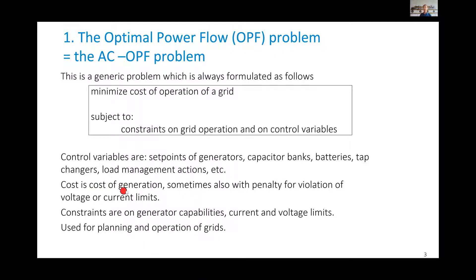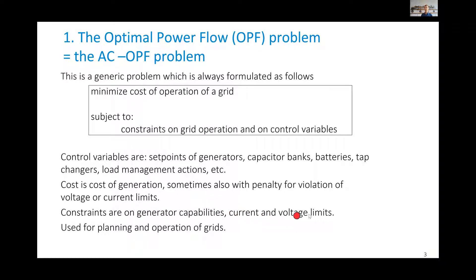The cost is classically the cost of generation. But often it also reflects other objectives — for example, if we are controlling voltage, the cost might reflect how close the voltage is to its standard value. Constraints include the power a diesel generator is able to produce, and constraints imposed by the grid in the form of current and voltage limits, which can sometimes be approximated by current limits or apparent power limits.